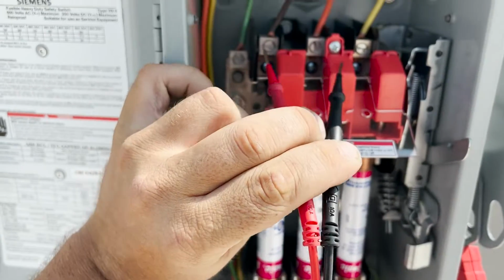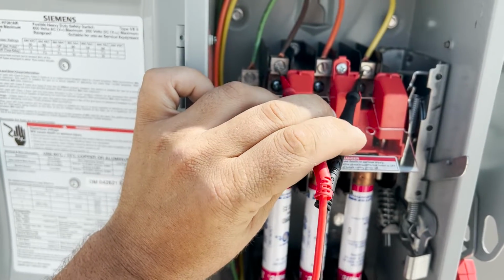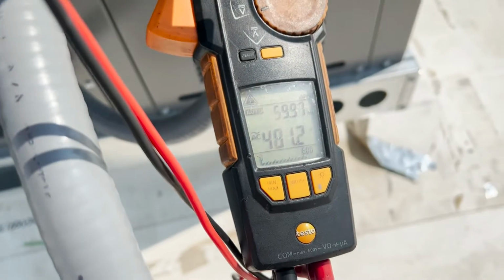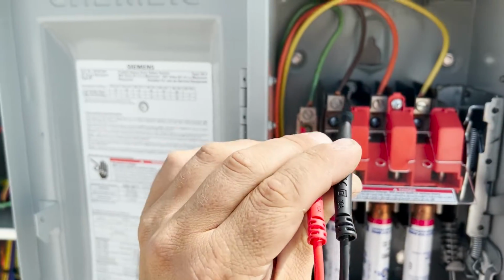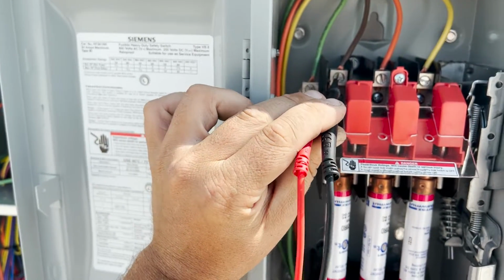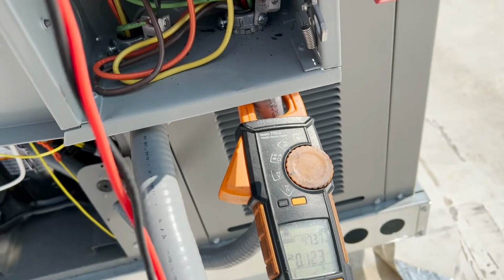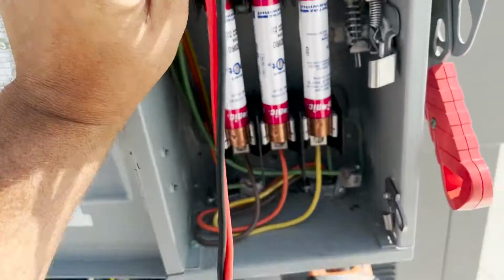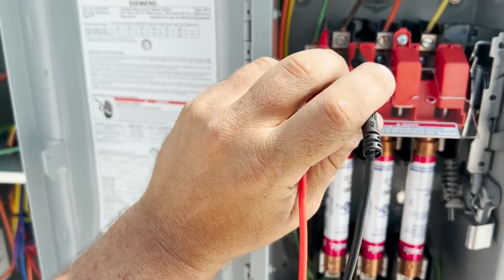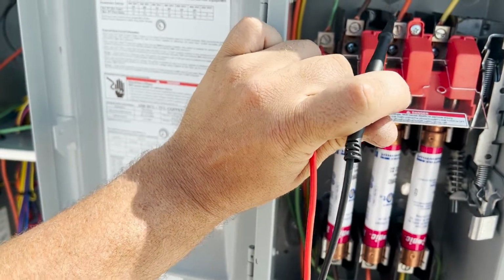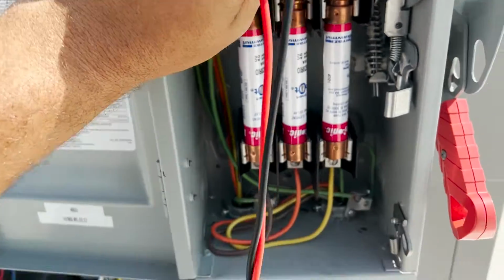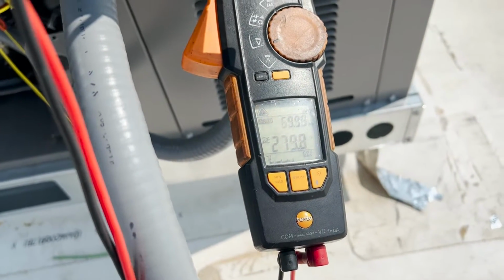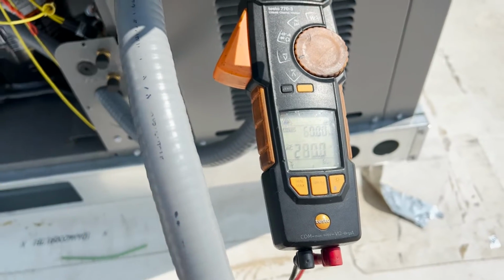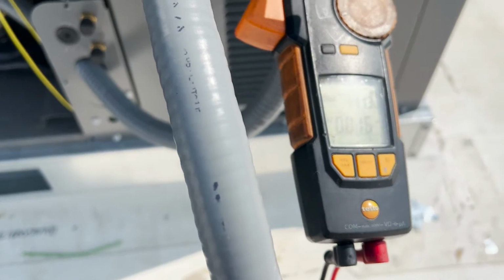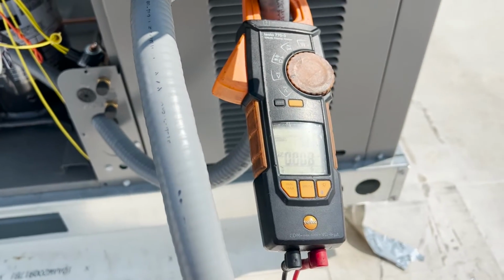Leg to leg, and then leg to leg, and then also leg to ground, leg to ground, and my chopstick skills. Leg to ground. Now that we know we have all 3 volt legs, we know that we're within 10% of each other, we're safe to turn this on and energize it into components.